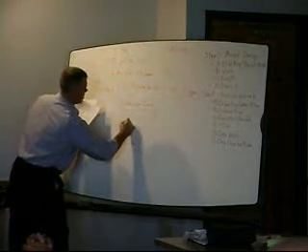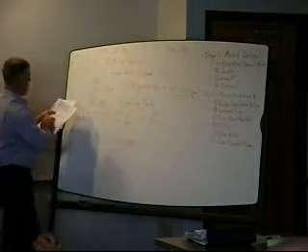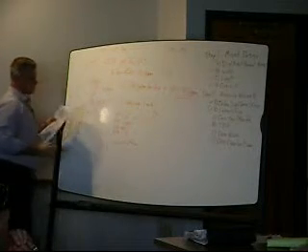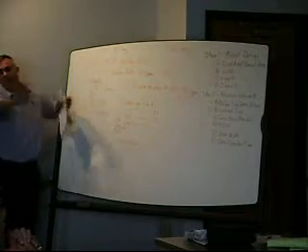This particular one came up with 10 foot of pipe. It's got 3 90s. This is straight pipe. This is fittings down here: 90-degree elbows, a gate valve, one of those, and a quick disconnect, one of those. Here's what happens. Perfectly straight pipe is 1-to-1, 10 foot of pipe is 10 foot of pipe. When you have 90s, every time you turn a 90, here we go. So we're in 2-inch pipe.